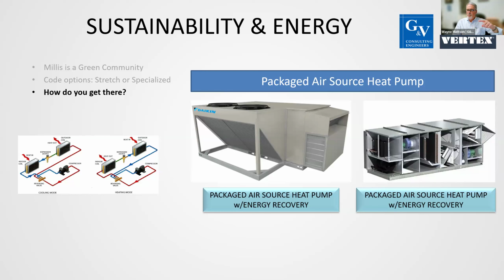So the outgoing airstream in the winter captures the heat of the air being exhausted. That wheel rotates into the fresh airstream, and then the air being brought in captures that heat, or the latent energy, to be delivered to the building. It's an energy-saving means of preheating and pre-cooling air to unload the central HVAC system. And regardless of whether it's a heat pump or hot water or chilled water, the principle still remains the same. So the equipment is very, very similar.